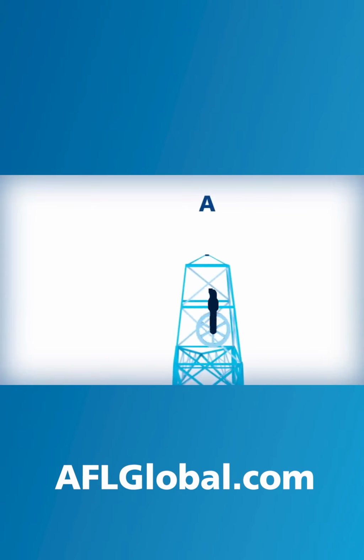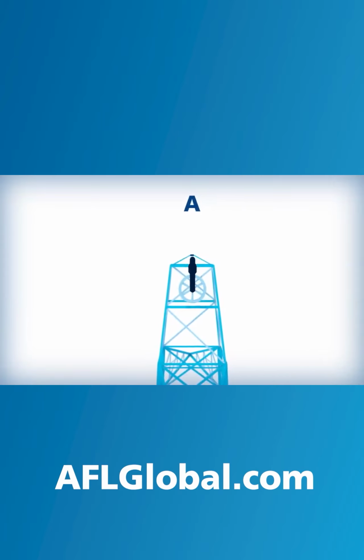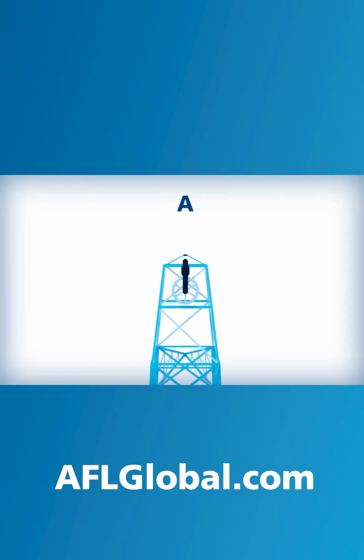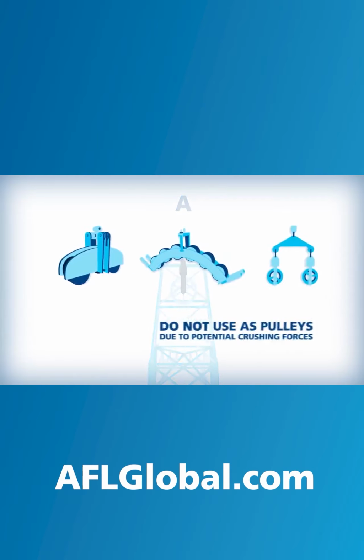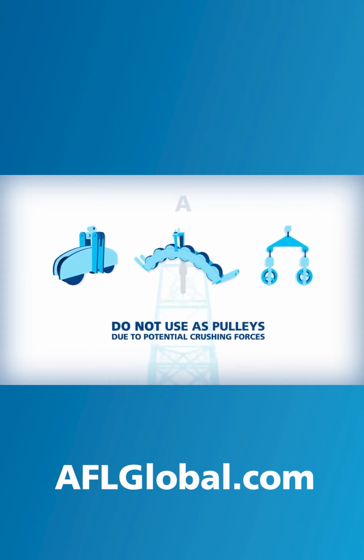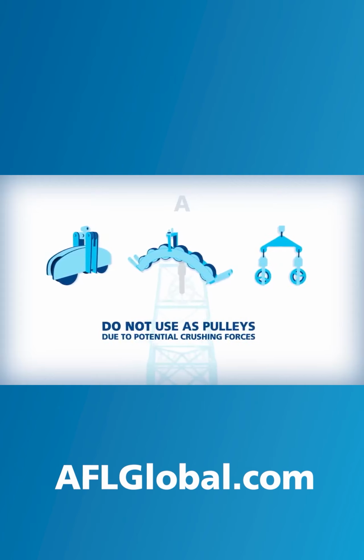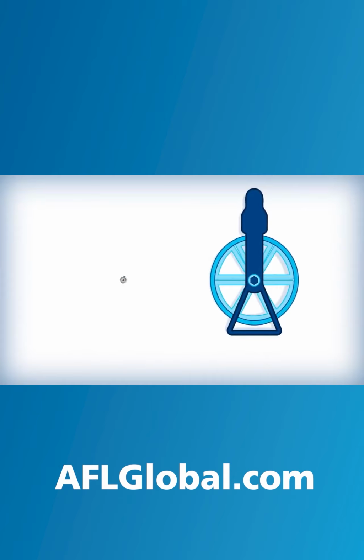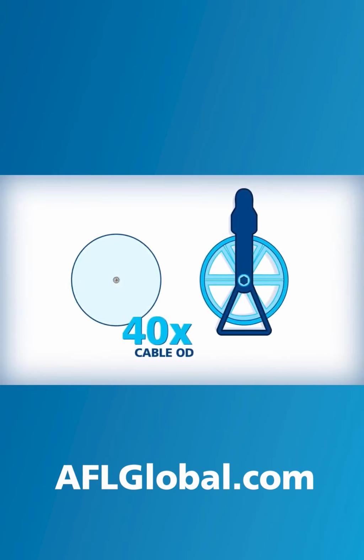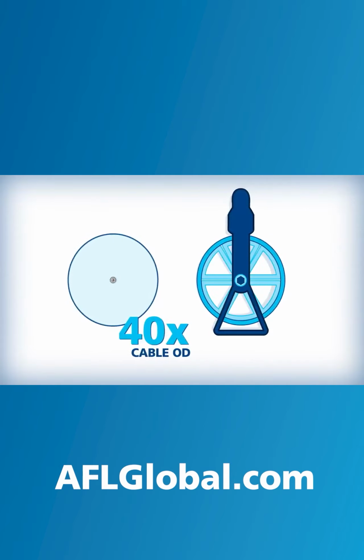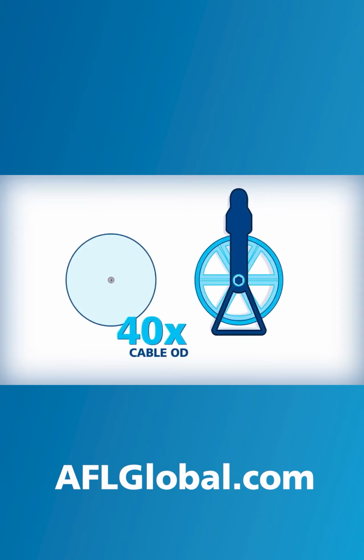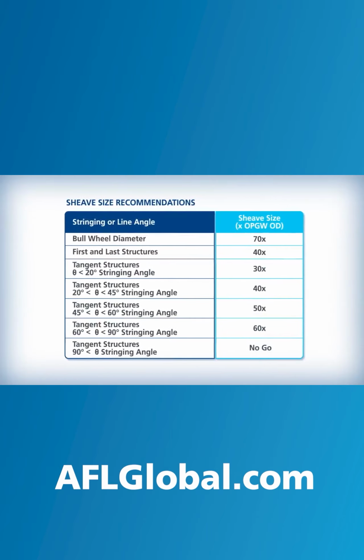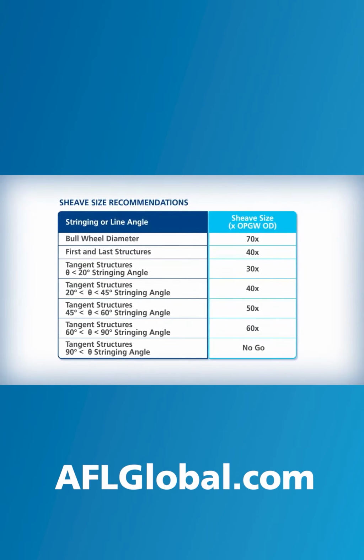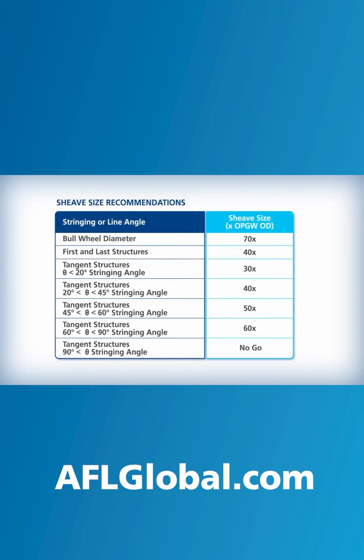Stringing blocks, or travelers, are mounted on the tower at the OPGW attachment point. Radius blocks, banana blocks, and array travelers should not be used as pulleys due to the potential crushing forces. AFL recommends a pulley with a diameter of 40 times the cable outer diameter at the first and last structures. Straight pulls can use a pulley with a diameter of 30 times the cable outer diameter.